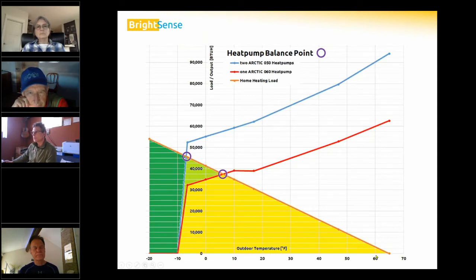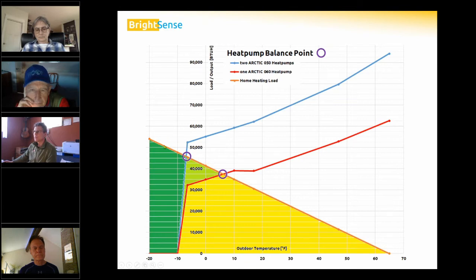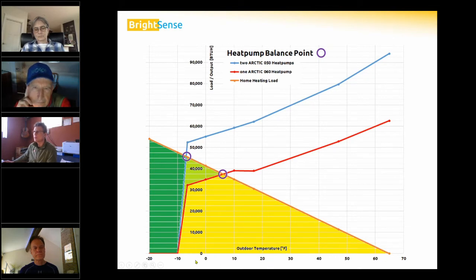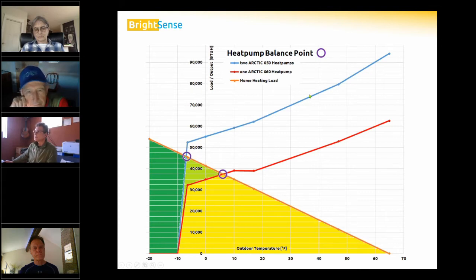The orange line illustrates the heating load of our building. At 65 degrees, we have no heating load. As it gets colder, our heating load increases. The outside temperature is displayed on the horizontal axis and the load on the vertical. These two curves shown are performance curves of two Arctic air-to-water heat pumps.